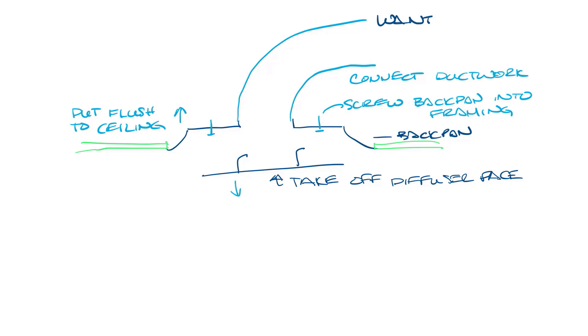Another note on the ductwork you need to think about is that you want the best possible inlet conditions when you install your diffuser to make sure you have good airflow and performance. You'll need some extra length in the flex duct to mount it on the diffuser before you put it in the ceiling because unlike a lay-in diffuser you're going to put the ductwork on first and then put it up in the ceiling. But you want to make sure you don't have too much that'll cause bad inlet conditions.